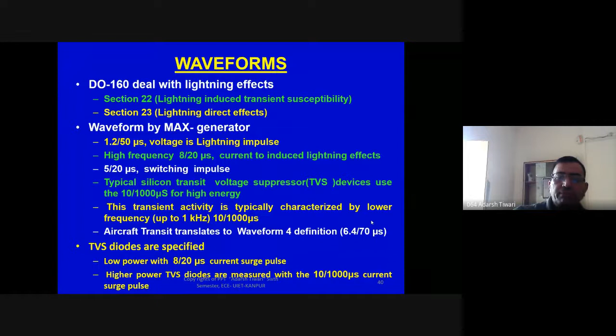So how does this stage vary? Now if the voltage level requires more, ultimately these stages will increase. This is how it is shown. This is the tail waveform and this is the rise. So now 10 by 350. This is a switching impulse and this is the direct effect. 8 microsecond rise time and 20 is the fall time.